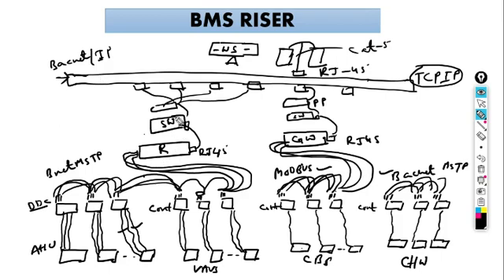From these routers, we can go to the switch and patch panel and to the wall socket. But in the case of Modbus or Profibus or CBus and other protocols, we use gateways because they are different protocols, right? Here it is TCP over IP. Here we don't have Modbus over IP. So to transfer from one protocol to a different kind of protocol, we need to have a gateway.